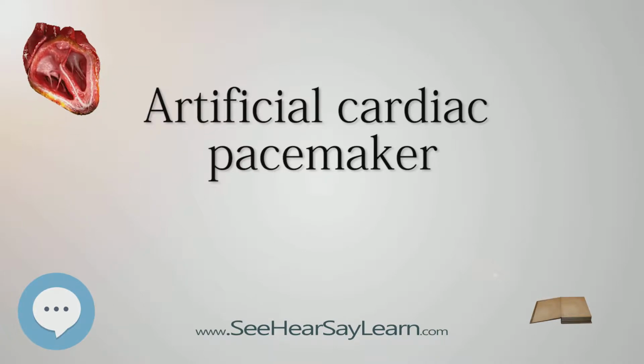Modern pacemakers are externally programmable and allow a cardiologist to select the optimum pacing modes for individual patients. Some combine a pacemaker and defibrillator in a single implantable device. Others have multiple electrodes stimulating differing positions within the heart to improve synchronization of the lower chambers, ventricles, of the heart. Methods of pacing. Percussive pacing.